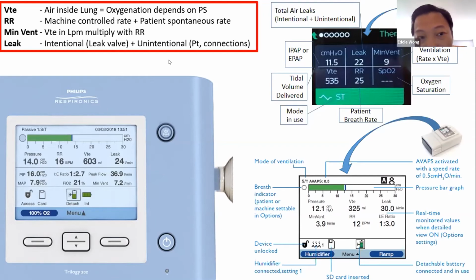Then there is the unintentional leak, which comes from the patient. Let's say for a tracheostomy patient, if the cuff balloon of the tracheostomy tube loses pressure, it will create leaks. If the tubing connection of the mask is loosened from wearing on the patient's face, it will also cause unintentional leaks. When we do suctioning, we open the suctioning port from the airway connector to perform suctioning.